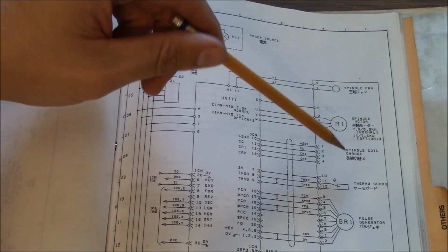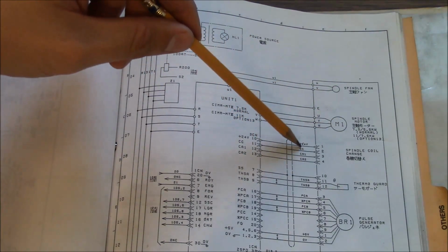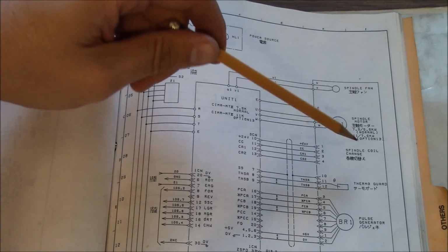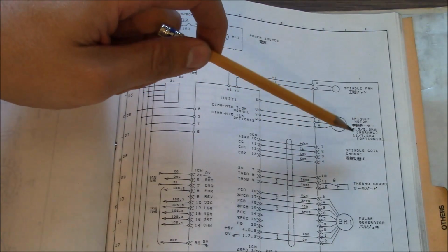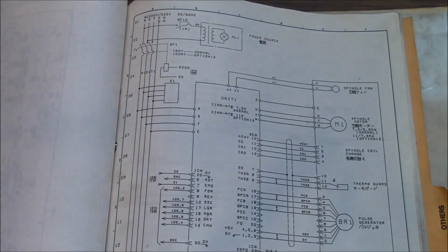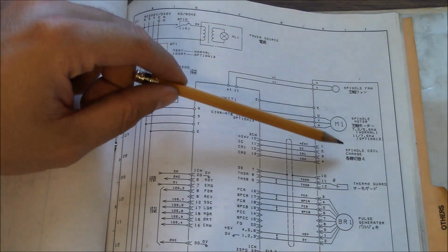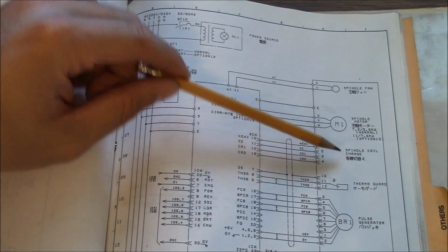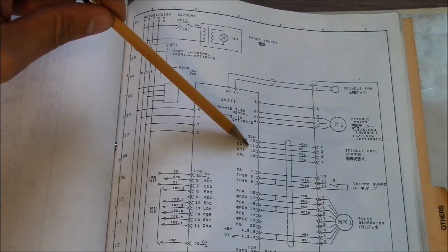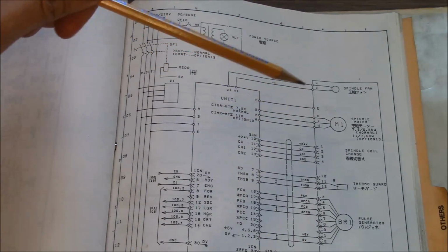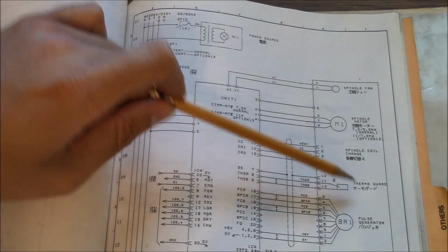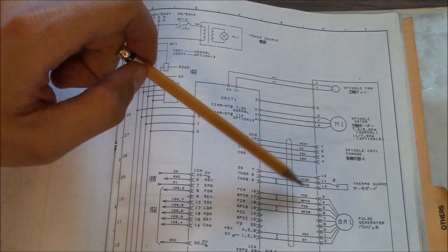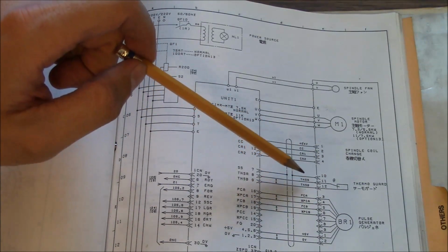And then it has these extra connections, CC, CR1, CR2 - they call it spindle coil change, but basically this is a Y-delta motor. So it's a 2-speed motor, and the drive automatically changes from Y to delta on the fly. This thing says thermal guard - that's a thermistor to shut down the motor in case it gets too hot.